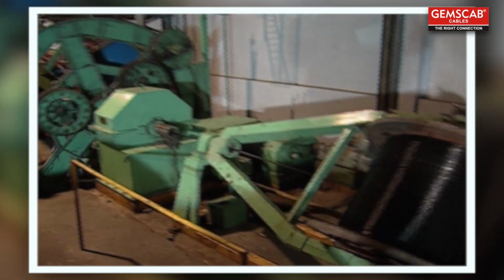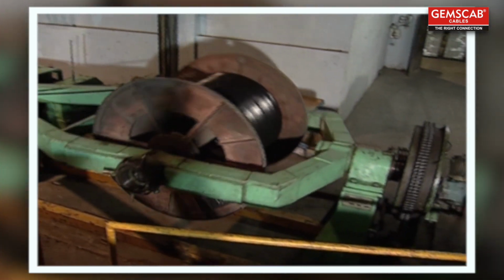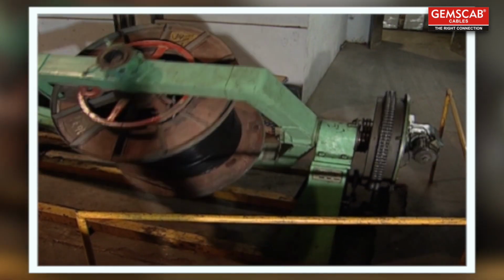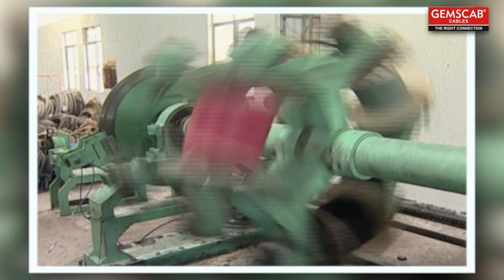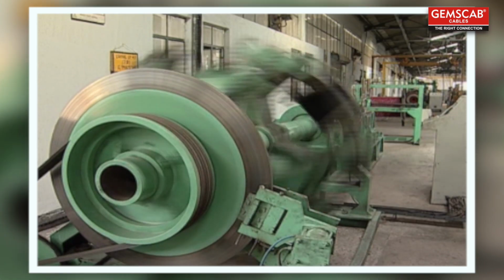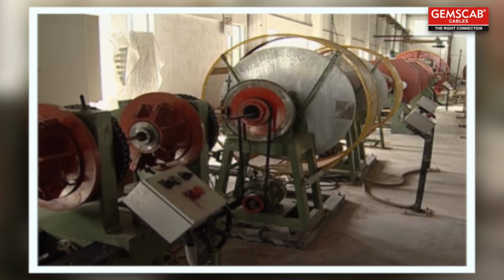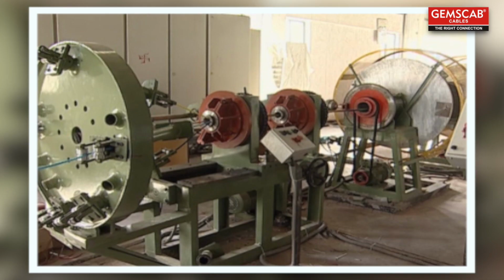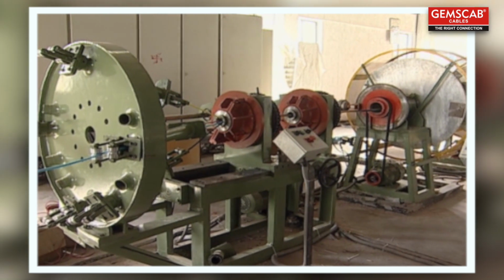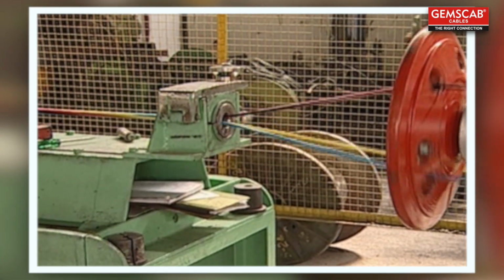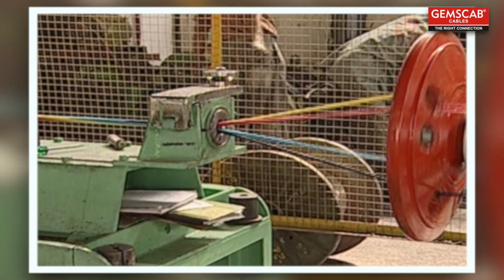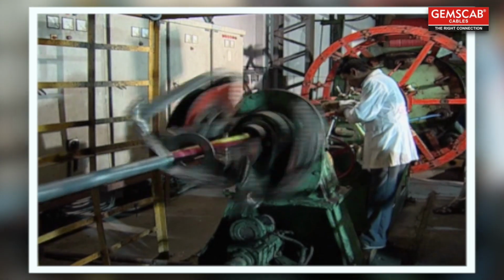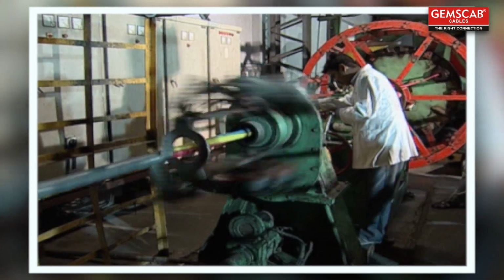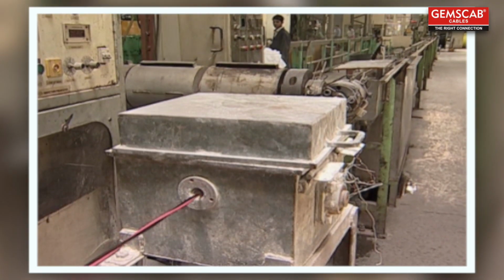LT power cables are combined in the planetary 3+2 laying up machines of 72 inches and 66 inches. Control cables are laid up in 2 machines of 7 bobbins capacity, 1 machine of 4 bobbins and 1 machine of 37 bobbins and 2 drum twisters, including a high-speed one for smaller sized power cables. In this process, all cores are combined into a single lot and carefully sheathed by the machine taping head for PVC tape inner sheath and on extruder for extruded inner sheath.